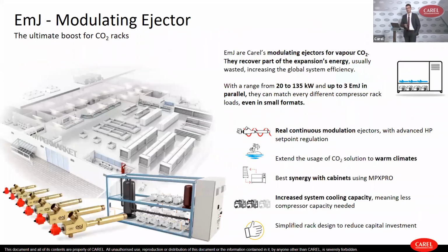Of course, if we would like to improve the efficiency of the unit in warm climates, but also in all the temperature profiles, we can fit our EMJ, our modulating ejectors. They are available in 6 sizes from 20 to 135 kilowatt. And you can put up to 3 ejectors in parallel in order to match the requirements in terms of capacity of your rack. The main feature of these ejectors compared to other solutions that are present in the market is the real continuous modulation. So this technology that is coming from our experience with electronic expansion valves is also present in the electronic modulating ejectors, and it is used to make the regulation very smooth and keep the working conditions of the rack very stable.